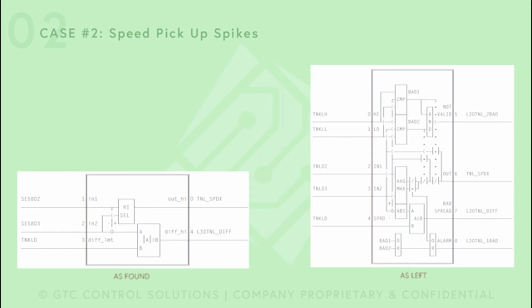The systems usually consider that one of the devices fails low. For instance, if they stop reading, the reading that you get is low. But we have seen devices can fail high. LVDTs can fail high, thermocouples can fail high, and speed pickups can fail high, as in this case.